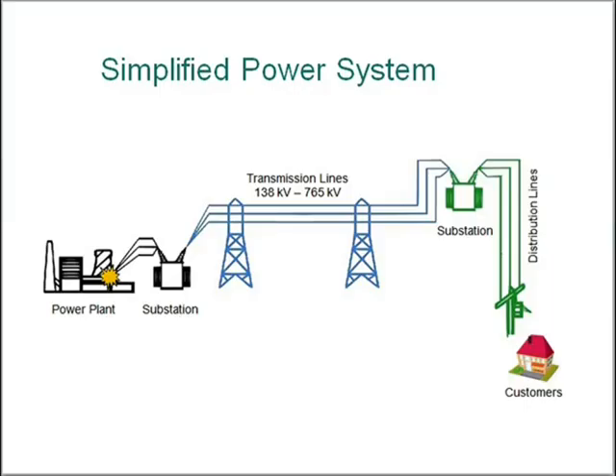Electricity is generated at the plant and transported by power lines to a nearby substation. In the substation, transformers increase or step up the voltage level to 138, 345, or 765,000 volts for transmission over large distances. The transmission lines connect to another substation within a few miles of customers. Here, voltage levels are reduced or stepped down to 34.5 or 12 kV for local distribution. Small transformers are connected into the distribution network to reduce voltage levels to the 110 and 220 volt outlets that power the appliances we use in our homes.